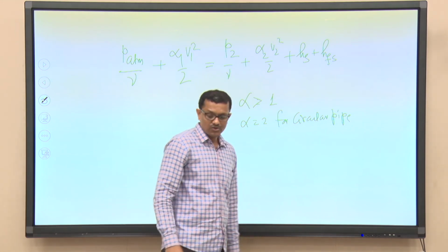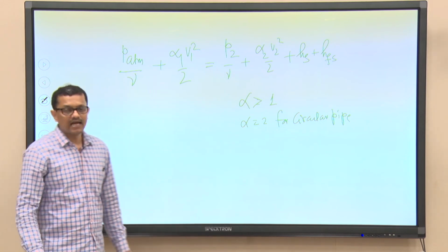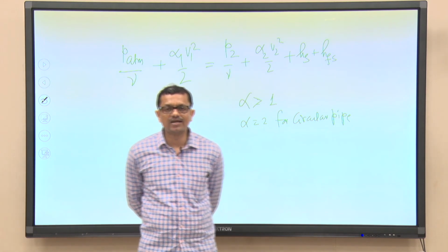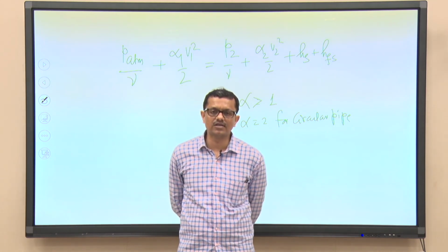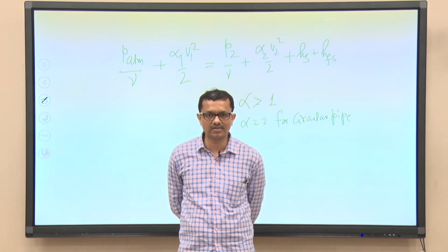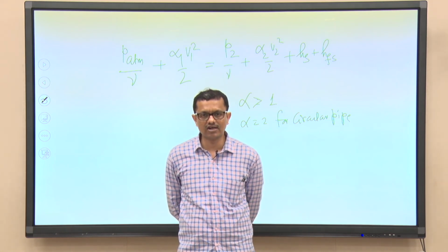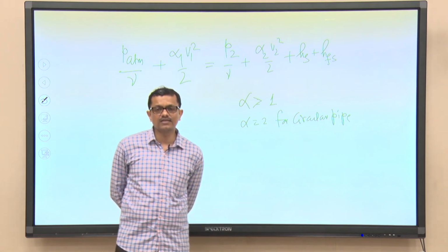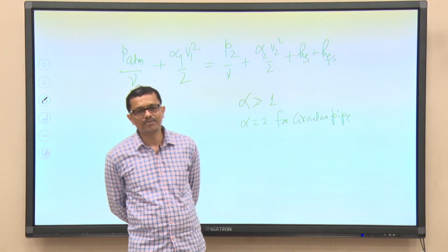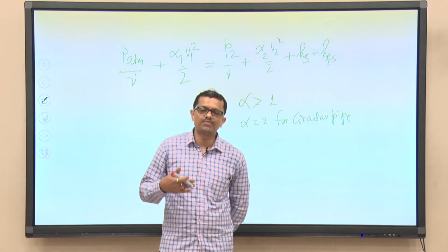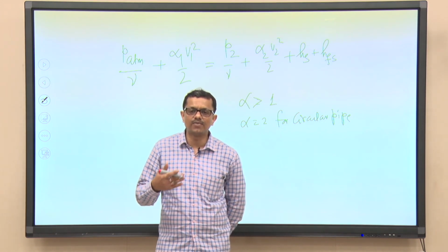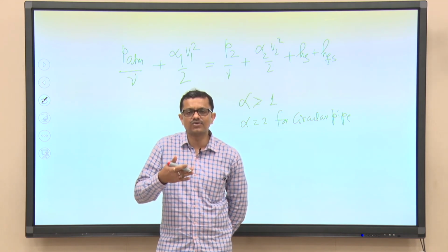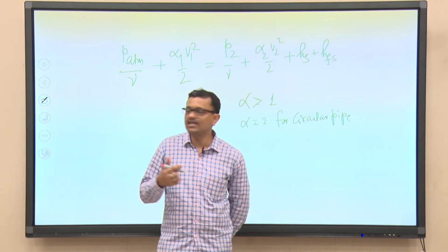So, what we have understood in today's class is that the pump should have a continuously drooping characteristic, and to have this continuously drooping characteristic, the losses due to separation at the pump suction side should be minimized, right. It cannot be completely reduced, but it should be minimized. To minimize it, the pump designer should design the pump properly, and if we are given a task to design a pumping station, then as engineers we should take into account all these effects.